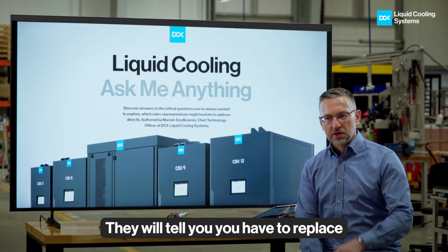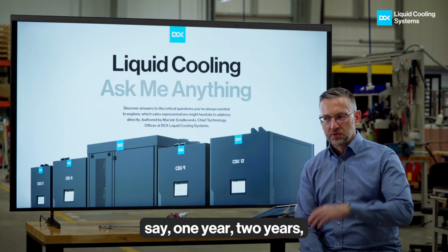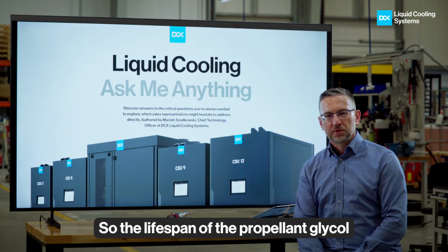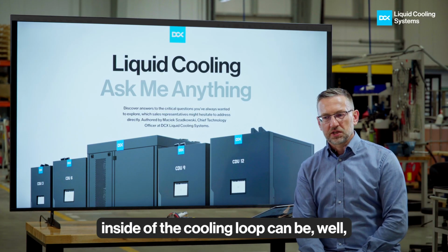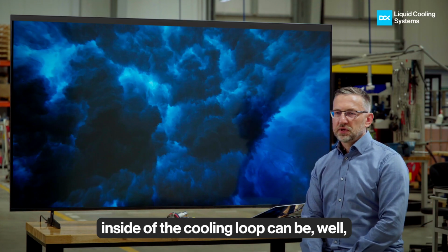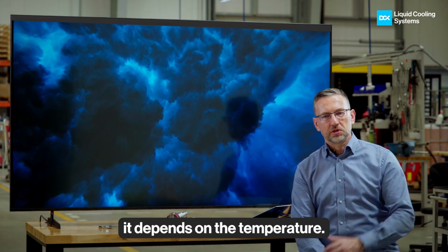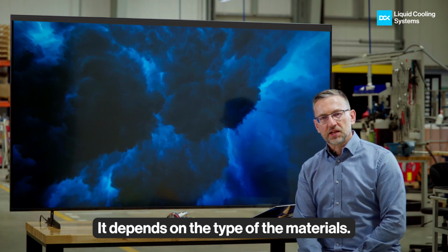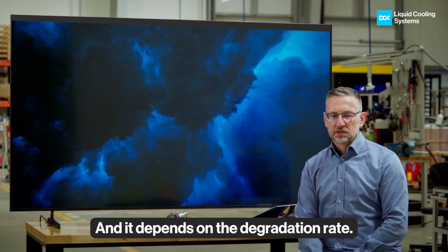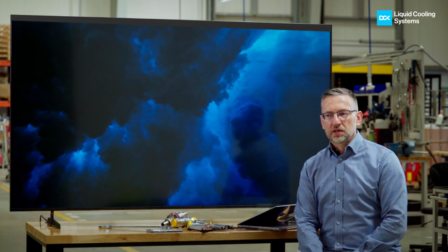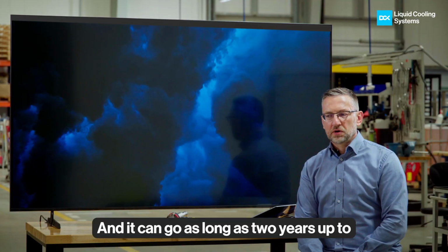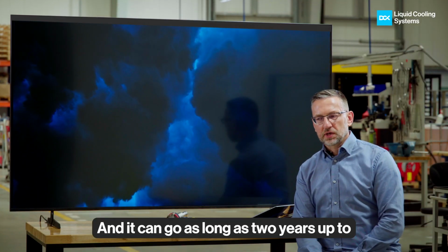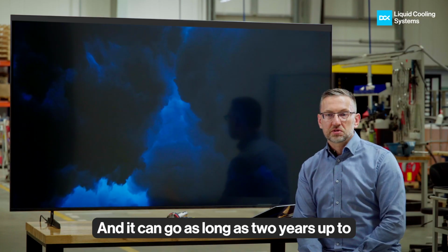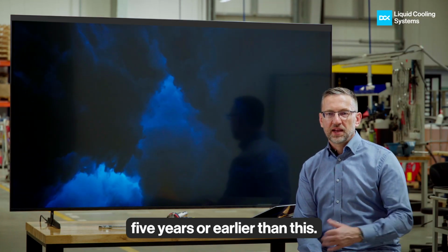They will tell you you have to replace your coolant in, let's say, 1 year, 2 years, 3 years. So the lifespan of the propylene glycol inside the cooling loop can vary, it depends on the temperature, it depends on the type of materials, and it depends on the degradation rate, and it can go as long as 2 years up to 5 years, or earlier than this.